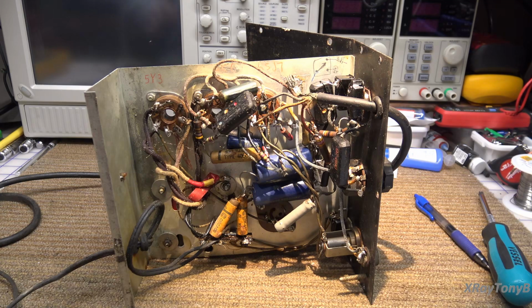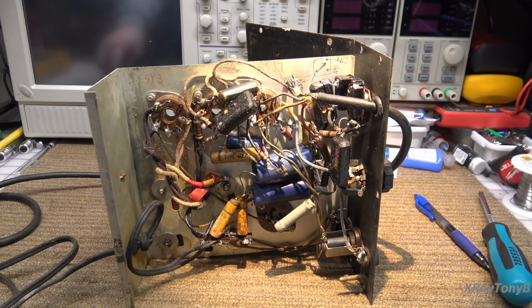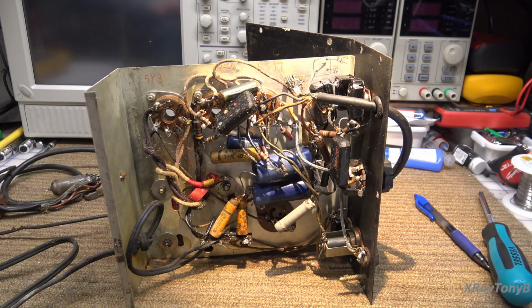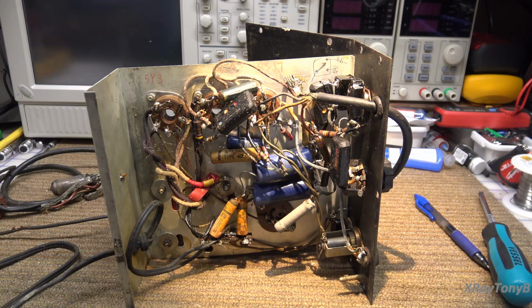We're going to plug this into a current limited supply and measure the output voltage. If we put this on a dim bulb tester, the bulb will not significantly drop the mains voltage. It'll drop a little, but not a whole ton, as long as there's no current being drawn—just the quiescent current that the transformer core and windings themselves will cause.